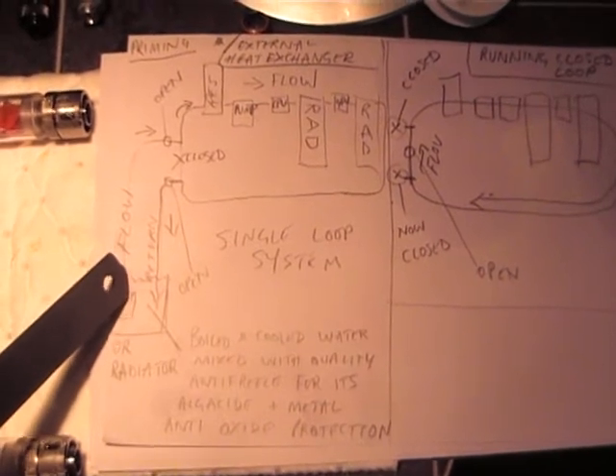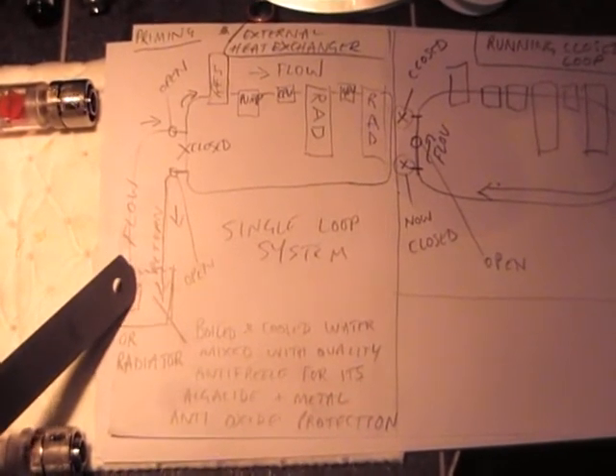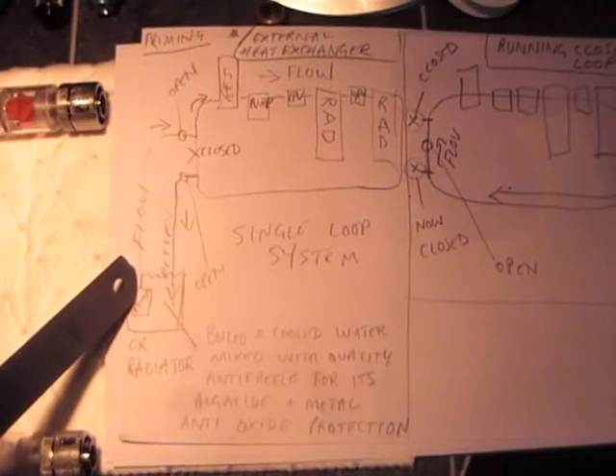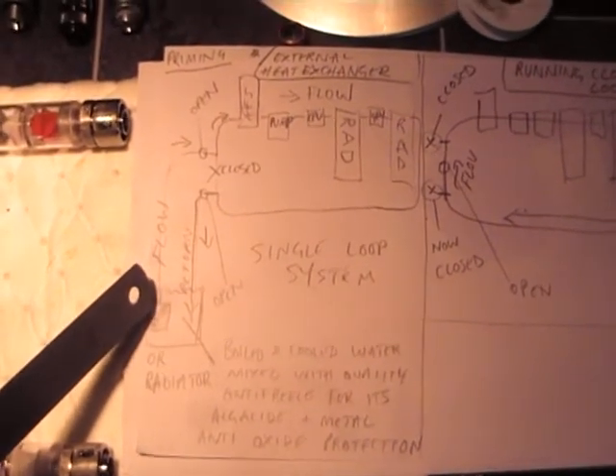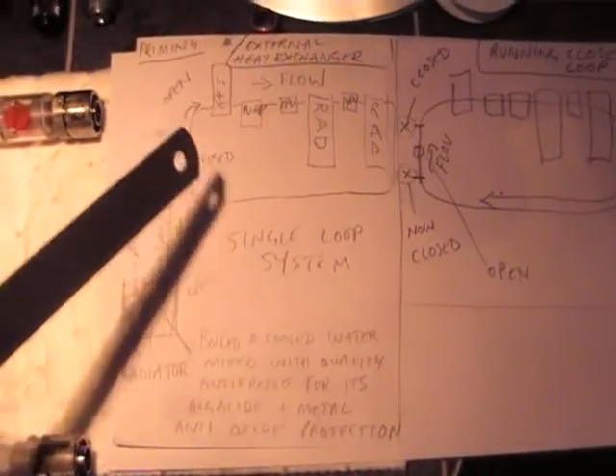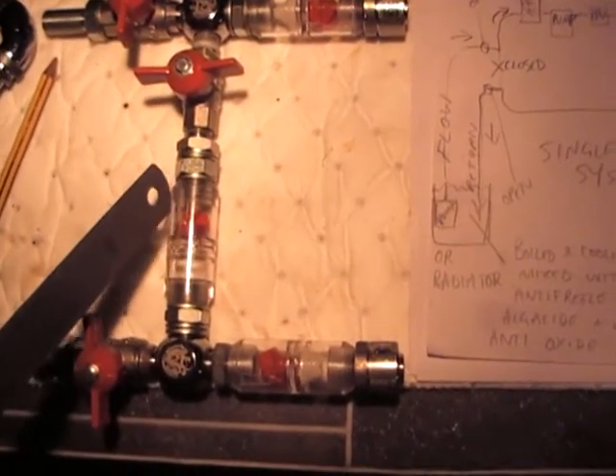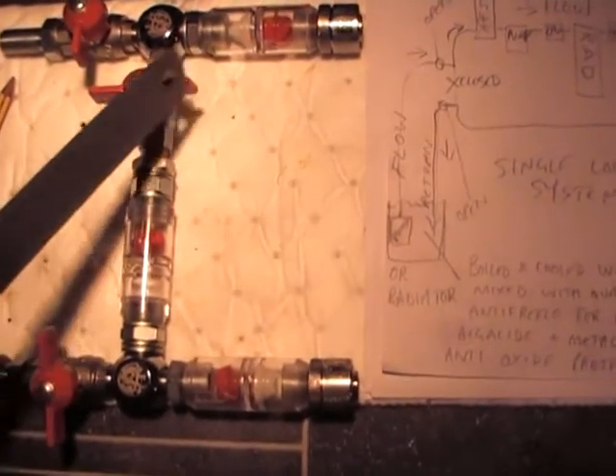By having increased pressure on this side, you could have a higher pressure pump if you've got a load of airlocks. And you can blow them out. And then once you've got your air out again, you could just close the valves, open this middle valve. And then you've got this spinner here that will show you that the loop is going round.